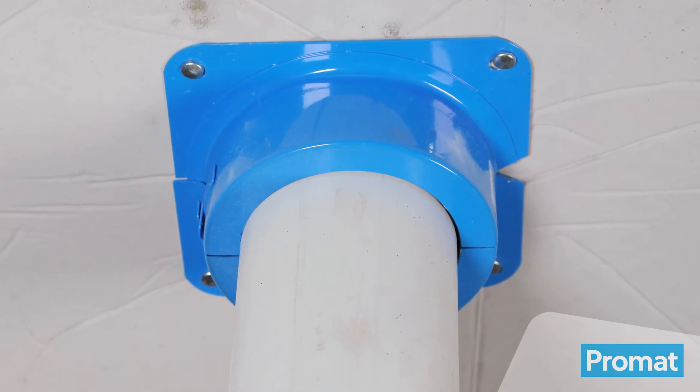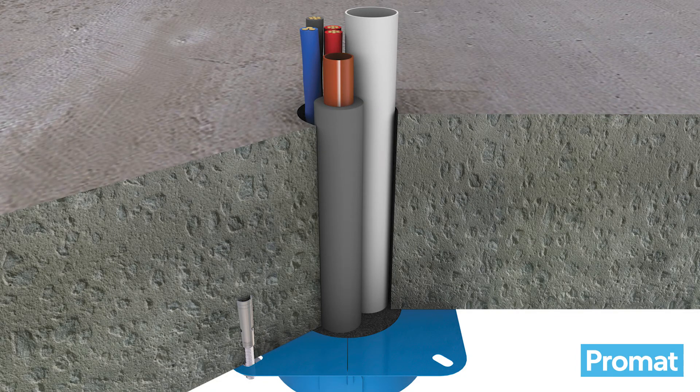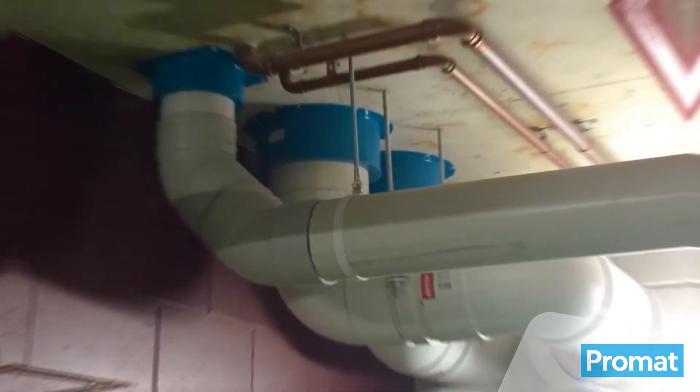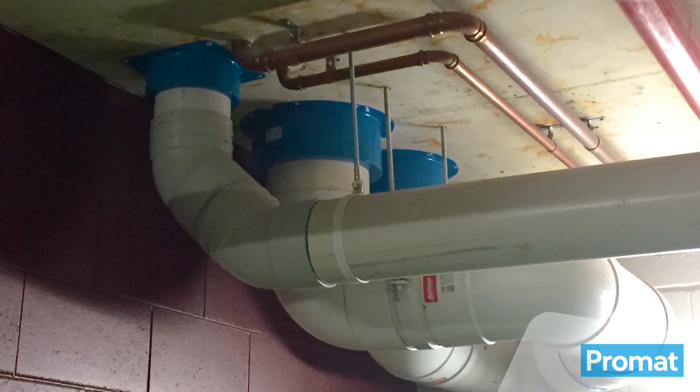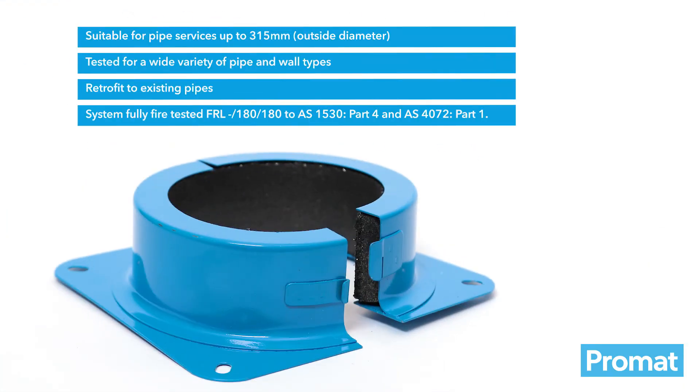The PrimaSeal Retrofit Collar is ideal for protecting a variety of plastic pipe types and sizes, along with cables, cable bunches and lagged copper pipes. It is approved and suitable for concrete slabs with a minimum thickness of 80 mm and can also be applied on slabs with permanent metal formwork such as Bondek. Its unique blue powder coated shell makes it easily identifiable and resistant to all environmental conditions.